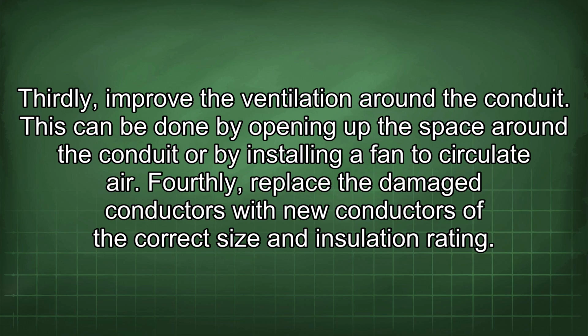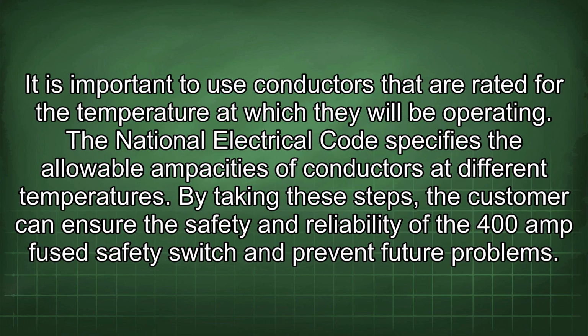Thirdly, improve the ventilation around the conduit. This can be done by opening up the space around the conduit or by installing a fan to circulate air. Fourthly, replace the damaged conductors with new conductors of the correct size and insulation rating. It is important to use conductors that are rated for the temperature at which they will be operating. The National Electrical Code specifies the allowable ampacities of conductors at different temperatures.